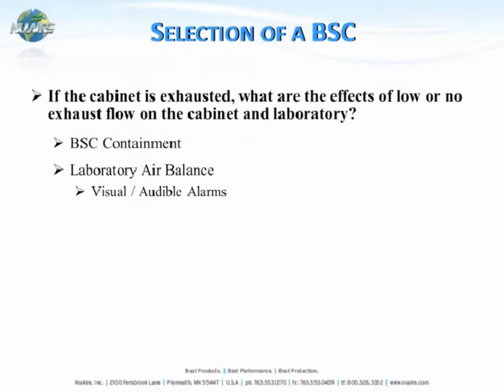Lastly, if the cabinet is exhausted, what are the effects on the cabinet of low or no exhaust flow, and on the laboratory itself? Consider how the cabinet performs if exhaust flow is lower or lost, how that affects laboratory air balance, and whether there are audible or visual alarms to let personnel know their safety could be compromised and they should exit the laboratory at that time.